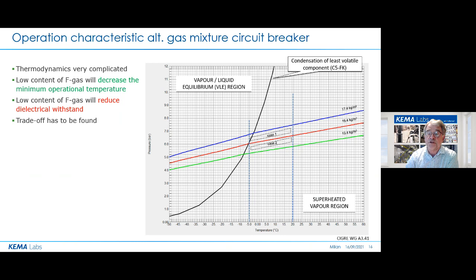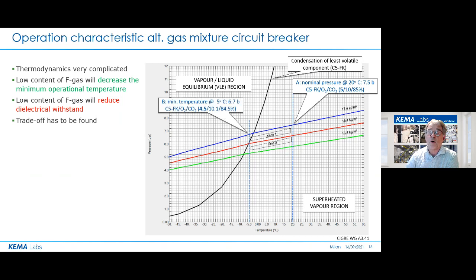The example chosen here is the C5FK. As can be seen, this component already starts to condense before -5 degrees. And therefore, at point B, the composition has already been changed from 5% C5FK to 4.5% C5FK. Care must then be taken that the reduction of the effective C5FK, which is 10% in this case, does not reduce the dielectric capability. Low F-gas content application at lower temperature reaches lower temperatures on the one hand, but it reduces the dielectrical withstand on the other.